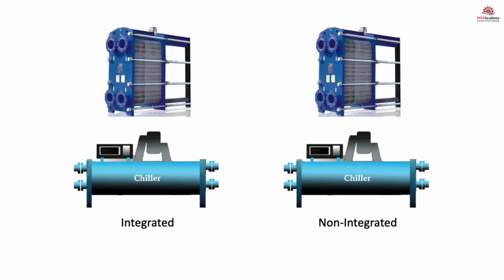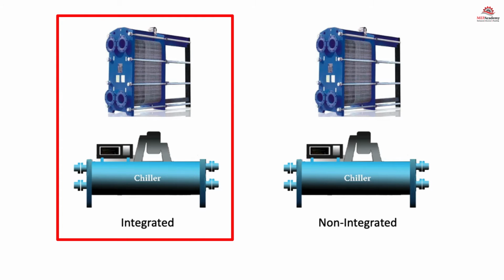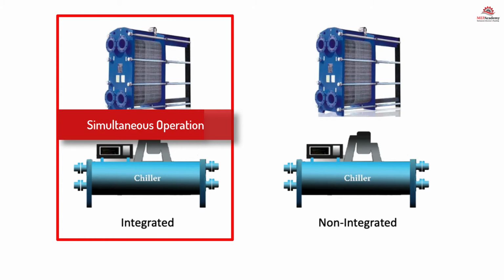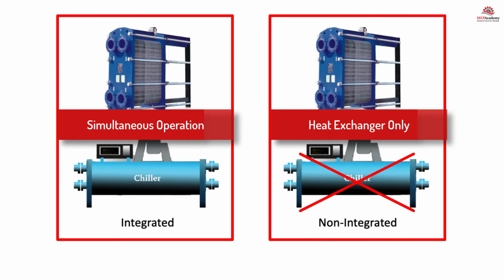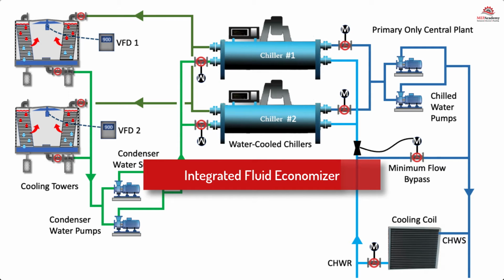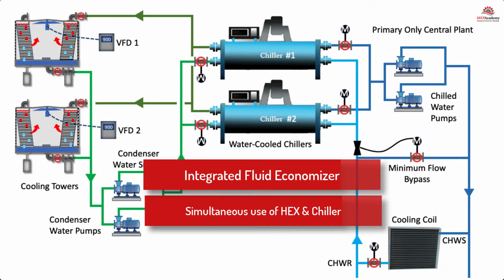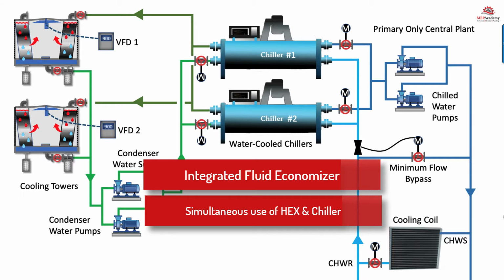There are several methods of operating a waterside economizer. One is for it to be integrated with the operation of the chiller, hence operating simultaneously, or non-integrated, where the chiller is completely off and the economizer has full responsibility to meet the demand of the load. Integrated waterside economizer. The use of an integrated waterside economizer allows for the simultaneous use of both the chillers and the reduced energy consumption aspects of a waterside economizer as required by ASHRAE 90.1.